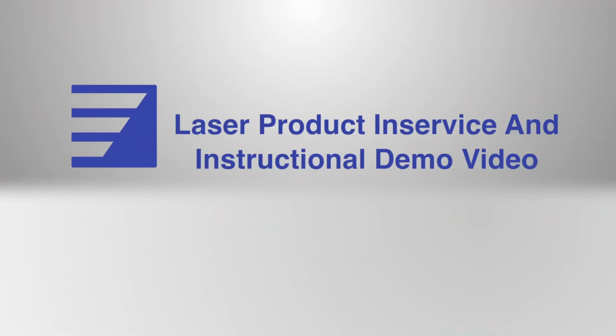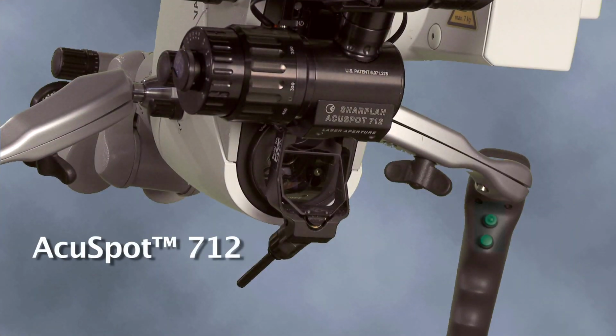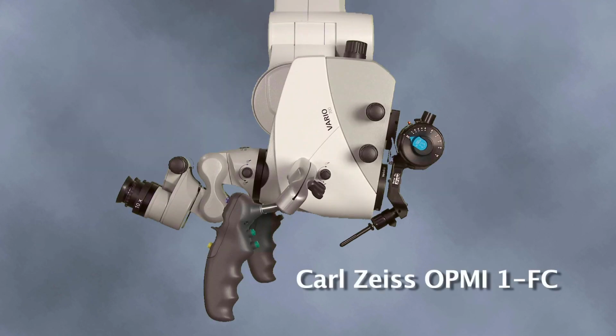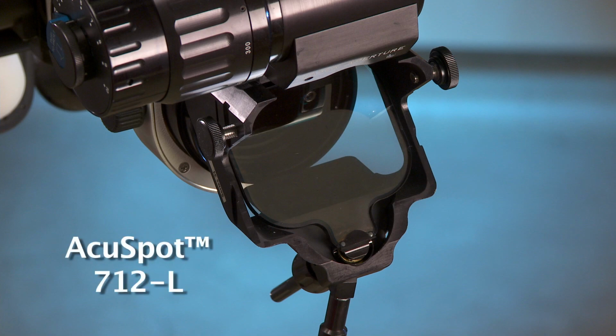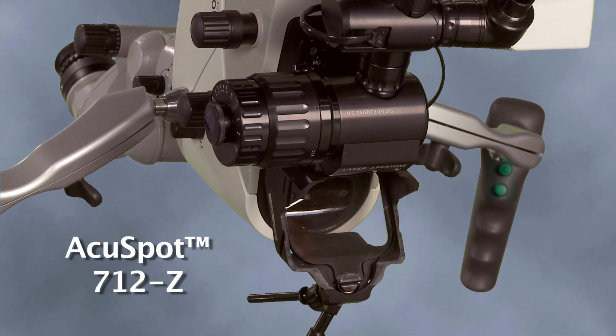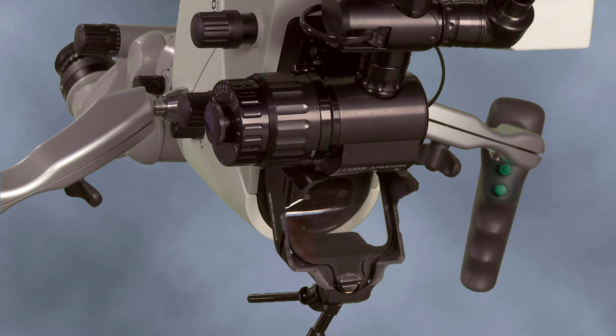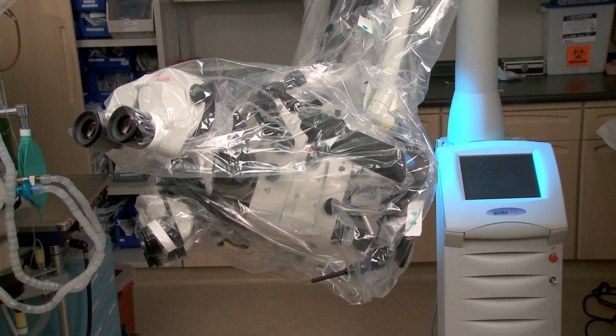There are three different AcuSpot CO2 laser micromanipulators. The AcuSpot 712 is used for microscopes with a small objective lens, such as the Carl Zeiss OPMI 1FC. The AcuSpot 712L and 712Z have a larger aperture for microscopes with larger objective lenses, such as the Carl Zeiss microscopes with 65mm outer diameter objectives and all Leica microscopes.